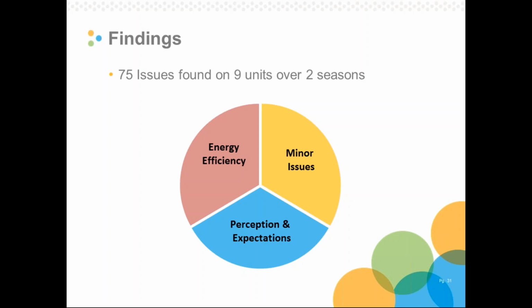All right, so what did we find? Well, we documented 75 issues on these 9 units over 2 full seasons. And fortunately for us, we can categorize these issues in some very easy groups, and they split up very evenly between the 3. About 33% of the issues we found had clear energy efficiency consequences. The energy recovery was reduced because of these problems, and that was associated with real energy losses and real cost penalties. About another third of the issues we call minor issues.